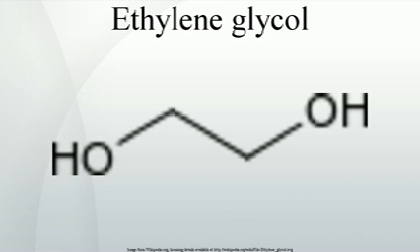The ethylene glycol either gains energy from the source — lake, ocean, water well — or dissipates heat to the source, depending on whether the system is being used for heating or cooling. Pure ethylene glycol has a specific heat capacity about one-half that of water, so while providing freeze protection and an increased boiling point, it lowers the specific heat capacity of water mixtures relative to pure water. A 50-50 mix by mass has a specific heat capacity of about 3,140 joules per kilogram·°C (0.75 BTU per pound·°F), thus requiring increased flow rates in same-system comparisons with water.